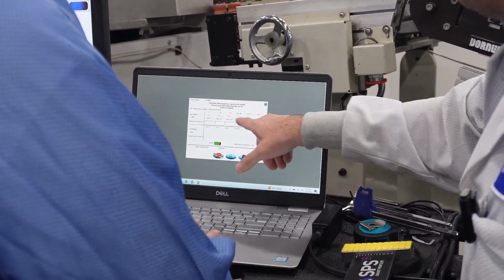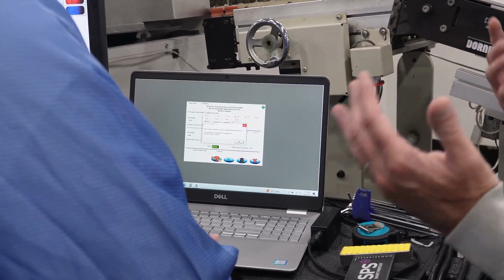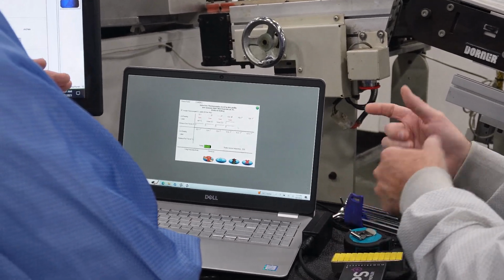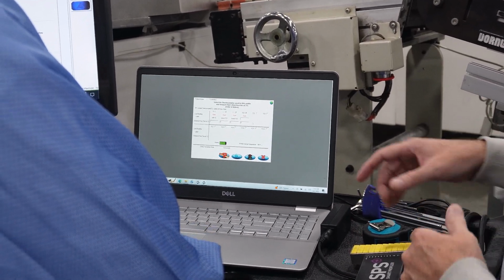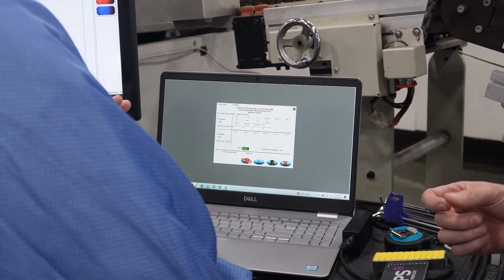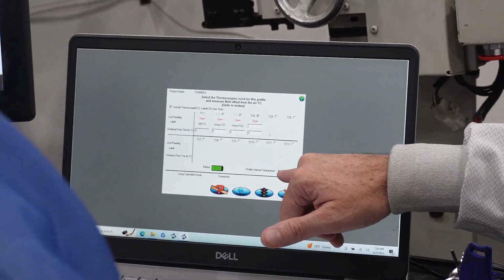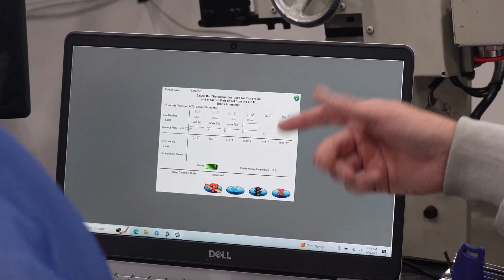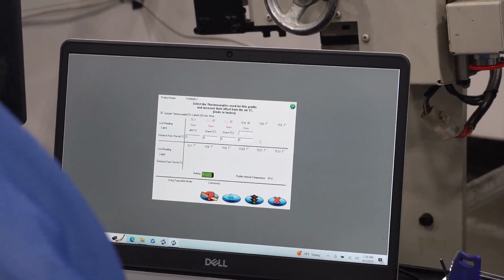Again, a good indicator, if there's anything red on here, that's an issue. And the more you get familiar with this, you'll see right away, oh, yeah, I know what that is. You know, I got to plug it in, or I got to fix that, you know, put a new TC on, or batteries got too little charge and then I need to plug it back in for a couple more minutes or something like that. Anything that's wrong will be in red on the screen. All right, and then you'll know, again, after experience, you'll know what to do to correct it. And then when you correct it, it'll go black, and then you'll know it's time to start, hit the traffic light and start that profile.